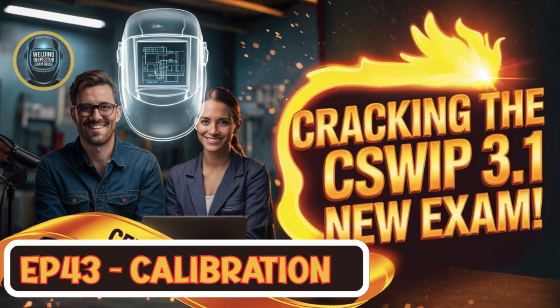Gotcha. Now, terminology, this is where I think it gets really important to be clear. Let's start with calibration. How does the standard define that? Okay, so calibration is defined as the operations for determining the magnitude of errors in a measuring instrument. And usually it involves actually adjusting the readings to minimize that error. Adjusting, okay. But here's the really crucial point. Only equipment that has actual adjustable output meters, those physical gauges you can see, can truly be calibrated.